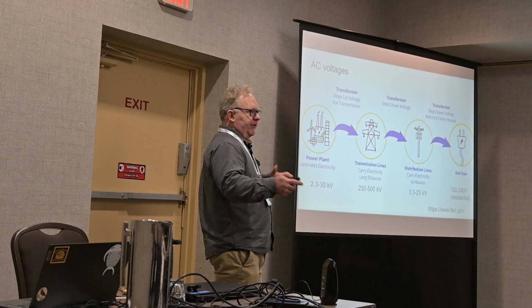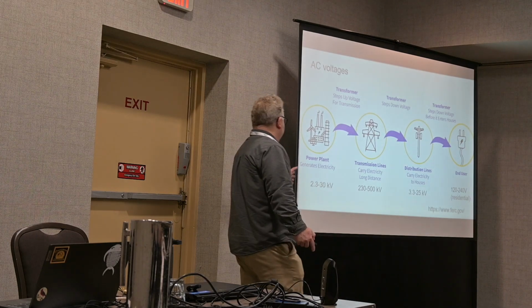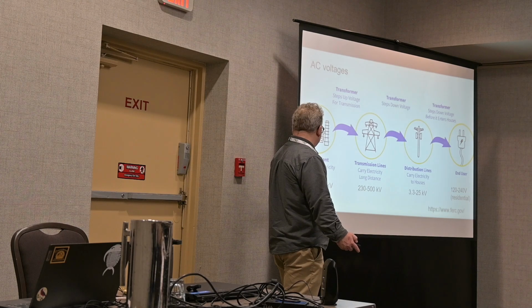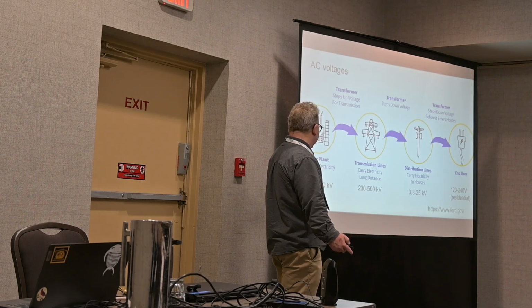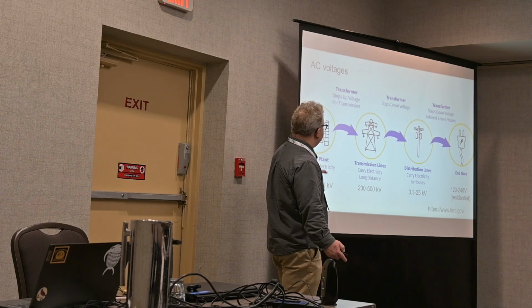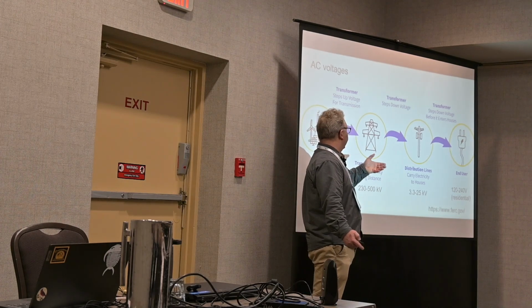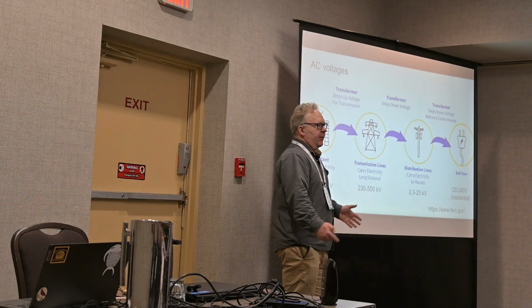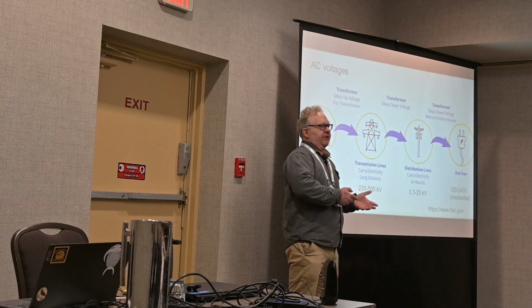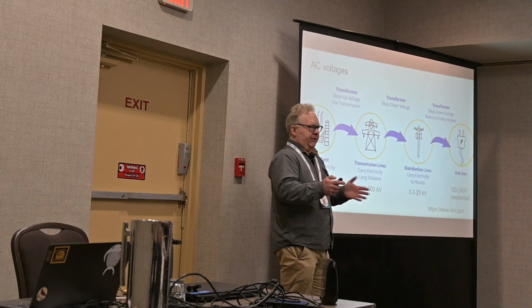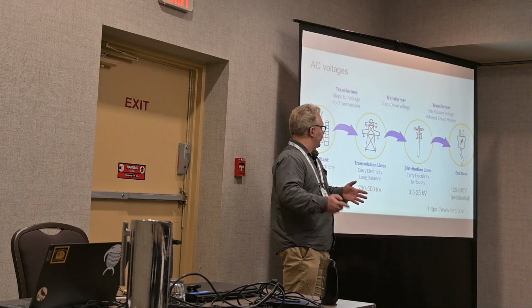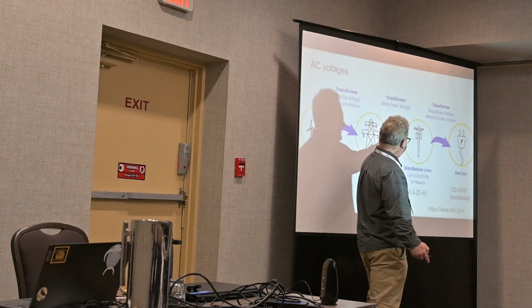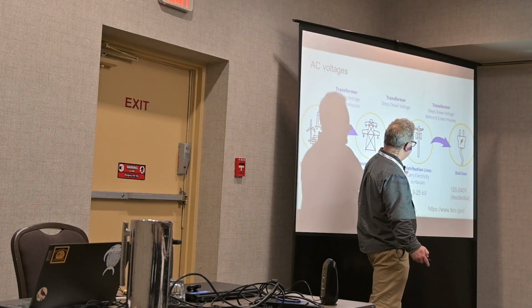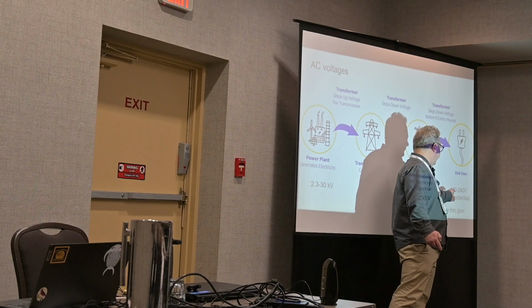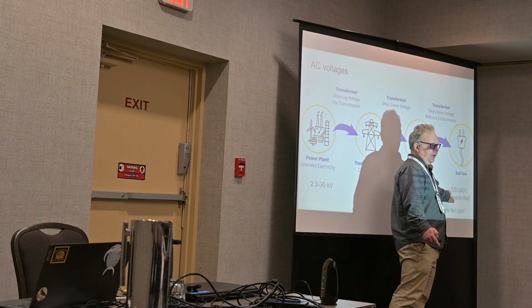The voltages change as we move around the grid. At the power plant, we have things in the range of anywhere from 2,300 to 30,000 volts. That gets stepped up when we go to the large transmission lines. It's stepped up because if we go to higher voltages, we can transmit more power with smaller currents, and that reduces line losses. As we get into our local distribution networks, it steps down. And then when we get into the homes, it's stepped down even further to the 120 and 240 volt currents that we see in the home.